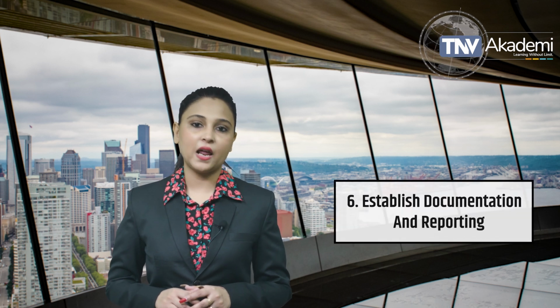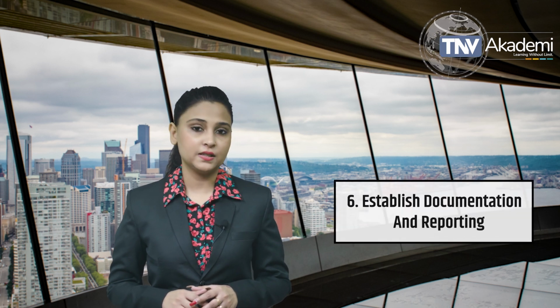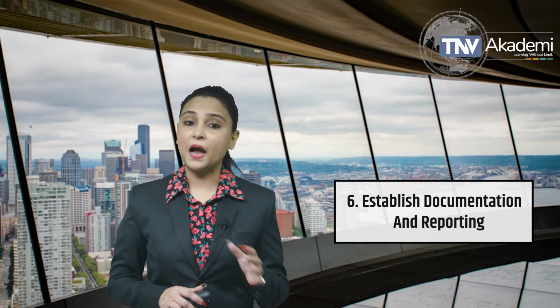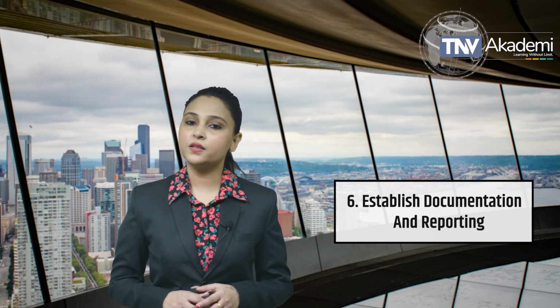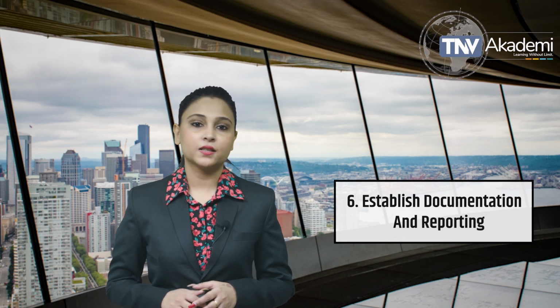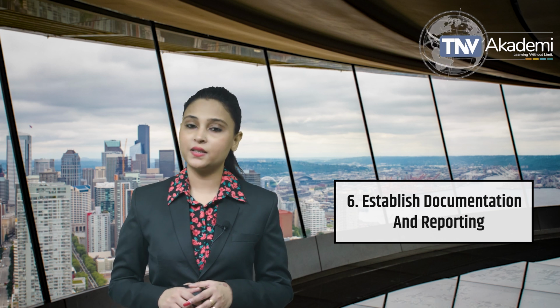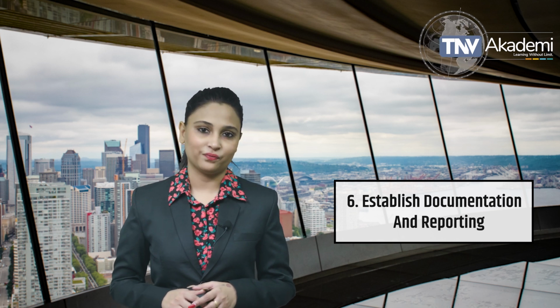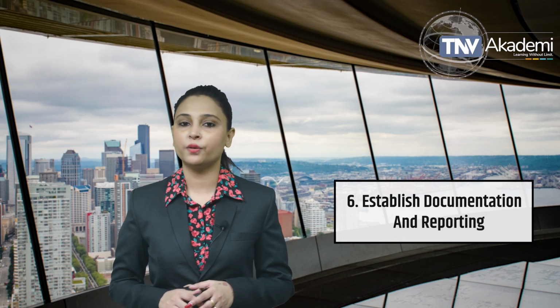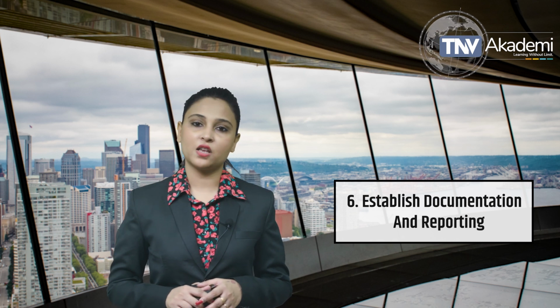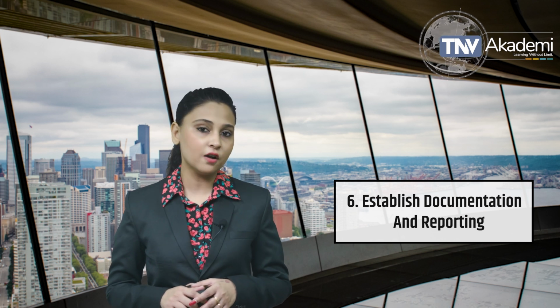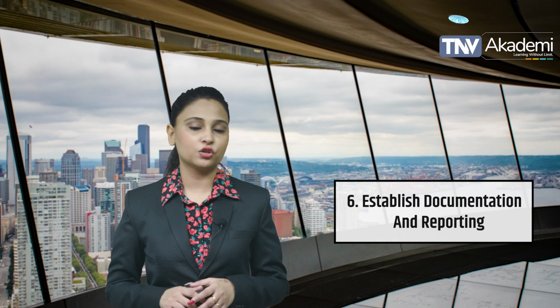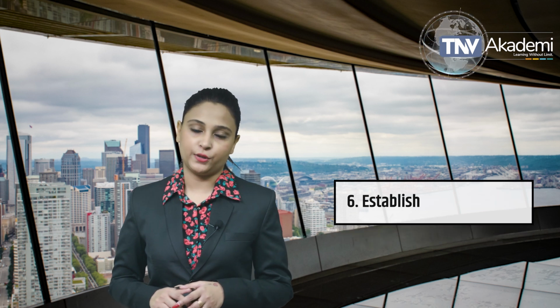Establish documentation and reporting. Document every step of the biological evaluation plan. This includes test rationales, test methods, results, and any risk controls applied. The resulting biological evaluation report provides a comprehensive summary of all evaluations and serves as essential documentation for regulatory submissions.